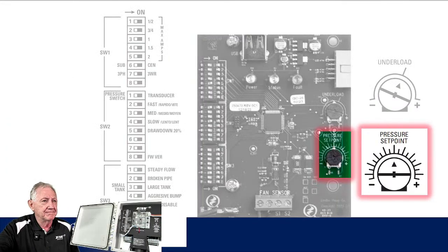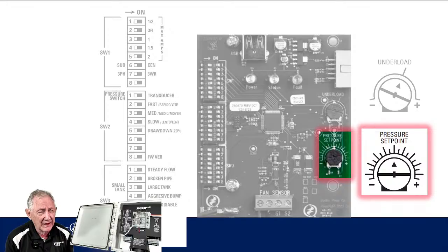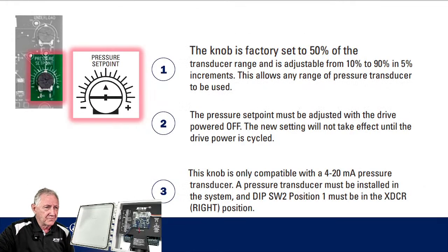Let's see. Okay, we're over here at the pressure set point. Now, this dial over here is going to be used only when a transducer is used. Again, when you're going to set the pressure with that switch, you're going to take that rubber boot off, look at the pressure gauge, and set the pressure there. With the pressure set point on a transducer, the knob is going to be set at 50%, all right? So now, listen carefully here. The transducer range is adjustable from 10 to 90%, all right? That's the range that's adjustable.